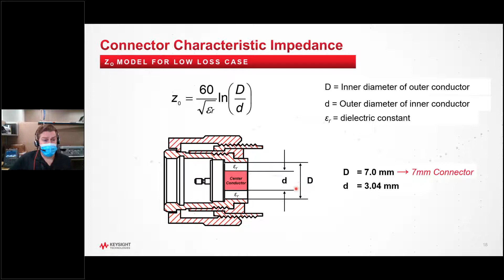The other equation governed by this connector geometry is the frequency coverage. In the case of the SMA, it's the ratio of the two diameters that determines the frequency coverage. This equation, 120 divided by your outer diameter, will give you roughly your highest frequency. Like I said before, there's a big range with some of them. SMA is the main culprit, where the manufacturer can specify SMA cables only good up to 18 gigahertz, while some go up to 26.5 or 27 gigahertz based on how precise their machining tolerance was and how much variability they have in their process.